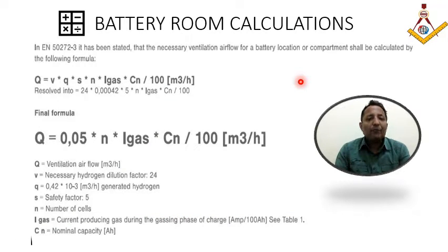A battery room is a very important aspect as far as marine offshore oil and gas is concerned. The battery room basically consists of batteries which are normally for the UPS system. These batteries play a very important role in having an uninterrupted power supply. The batteries always need to be charged, and when battery charging happens, it releases a certain amount of hydrogen, which is a hazardous gas.